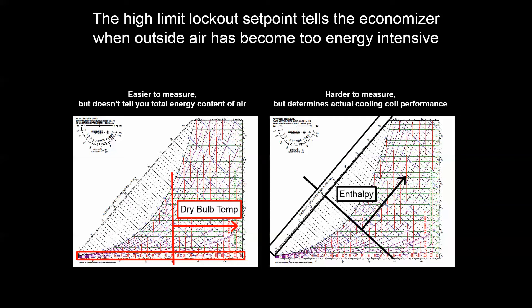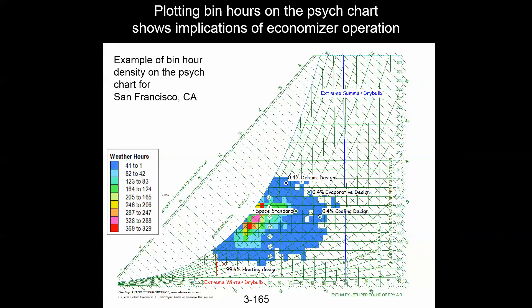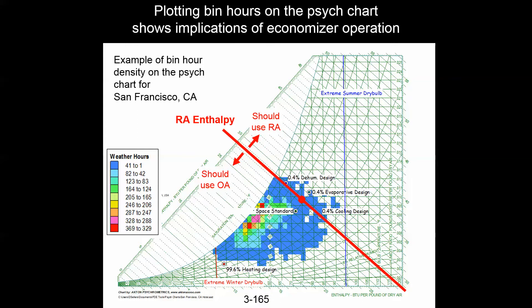Oftentimes we make a compromise. Looking at bin data, we select an economizer lockout temperature. We start by defining the design return air condition — in this case 75 degrees and 50% relative humidity — which has a specific enthalpy associated with it. Ideally, whenever outside conditions are below that enthalpy we'd be using outside air, and whenever outside conditions are above that constant enthalpy line we'd be using return air.